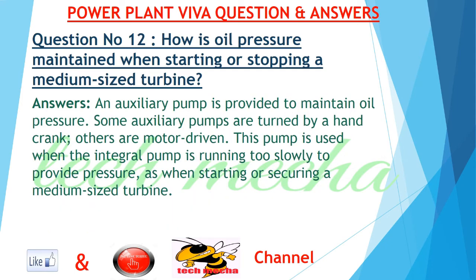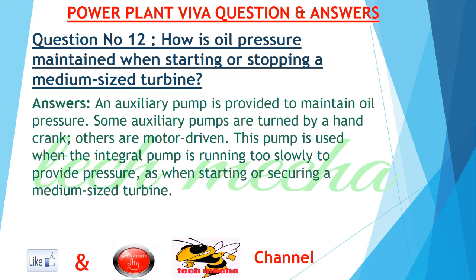Question number 12: How is oil pressure maintained when starting or stopping a medium-sized turbine? Answer: An auxiliary pump is provided to maintain oil pressure. Some auxiliary pumps are turned by a hand crank; others are motor driven. This pump is used when the integral pump is running too slowly to provide pressure, as when starting or securing a medium-sized turbine.